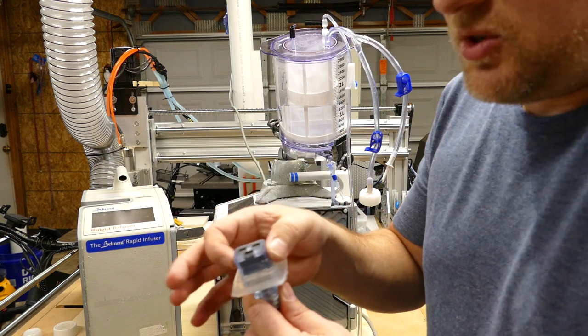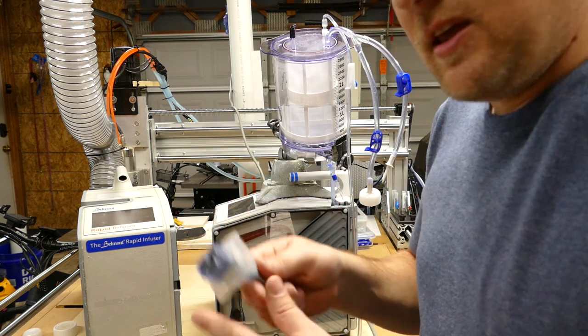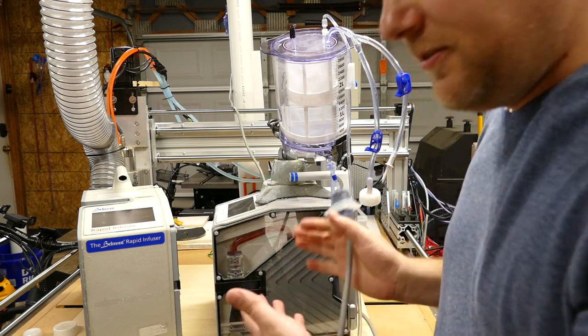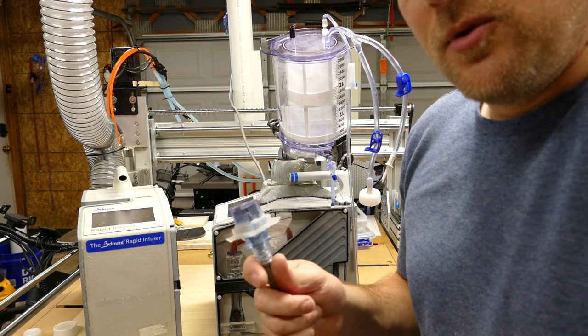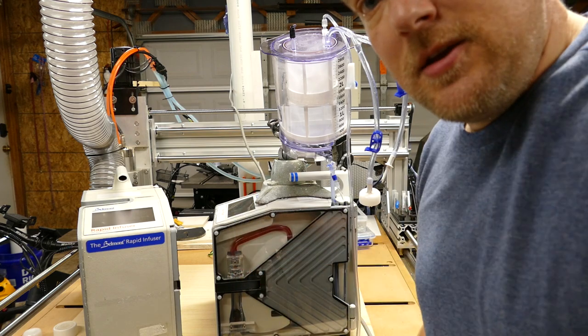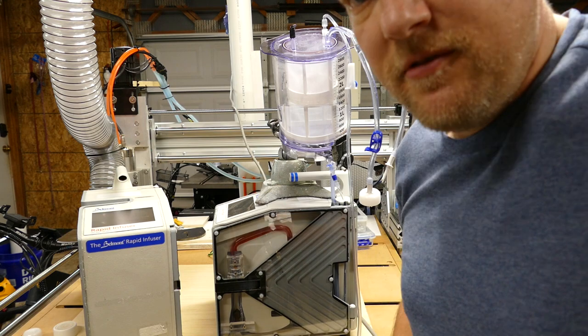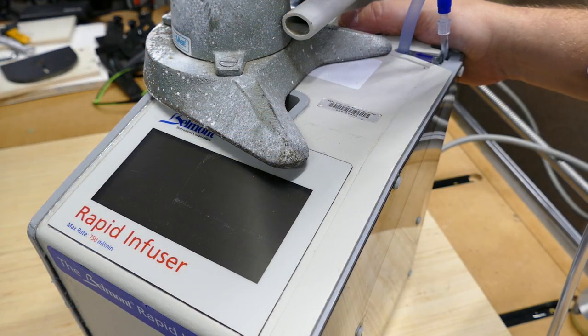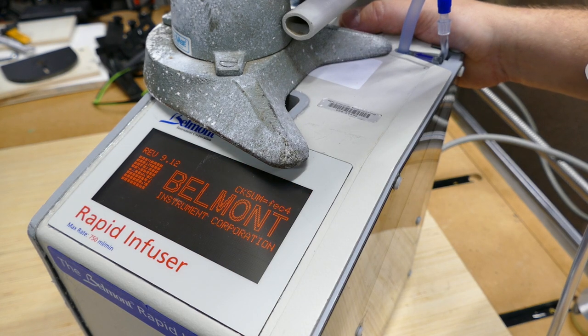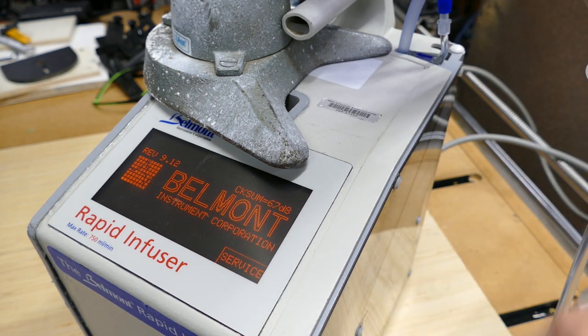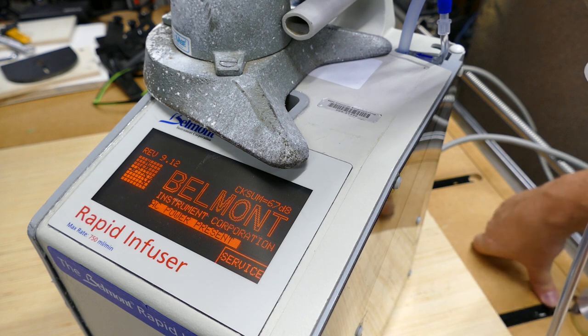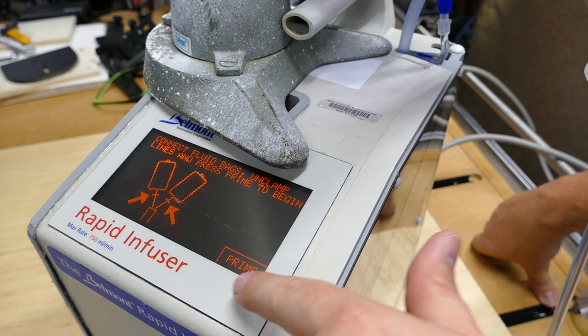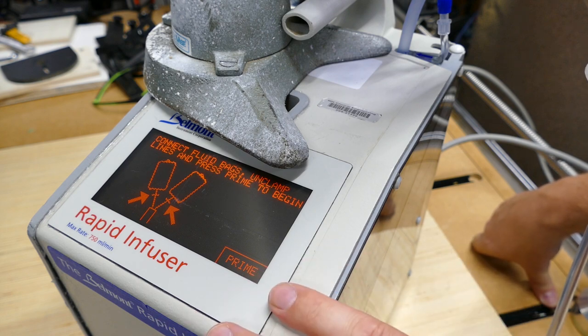And it normally has some retention straps on the side that keep it from falling out, because you definitely don't want this guy to quit working. Although, it does have an integral battery. We'll cover that later. So we're going to go ahead and turn the unit on and set it through its paces. We're going to give it a check out. You can see here it's got the old school monochrome style display. It does its pre-service checks. And there was actually a button down here, so you can go into service mode.